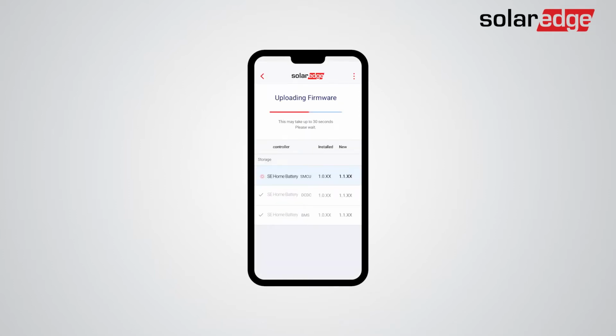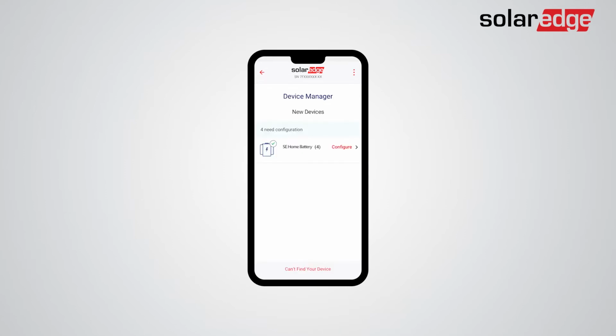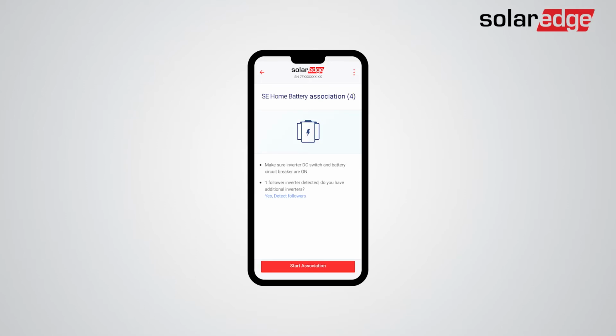Next, the battery firmware will be automatically upgraded. Note that this may take a few minutes. Once firmware upgrade is completed, you can continue with the configuration of the battery. As the configuration wizard applies to all inverters on site, you will be prompted to detect follower inverters. In this demonstration, a follower inverter has already been detected.